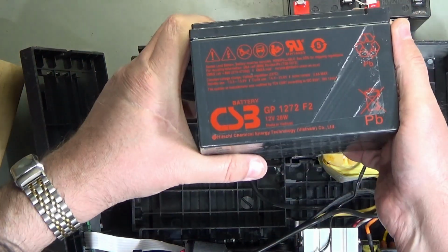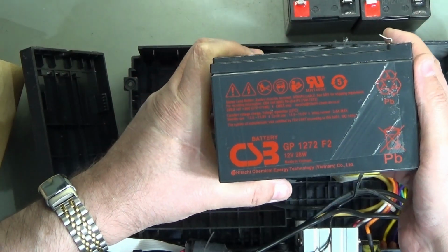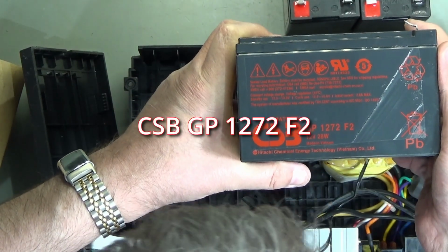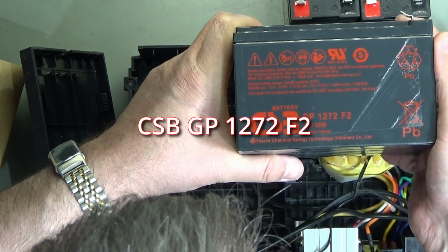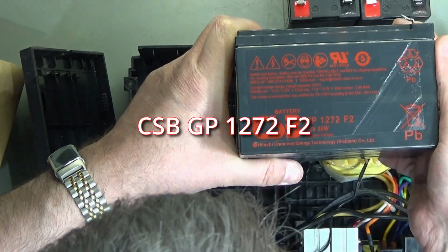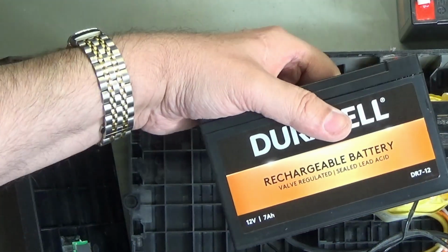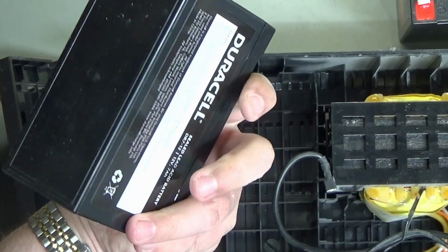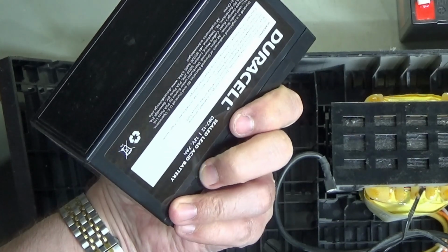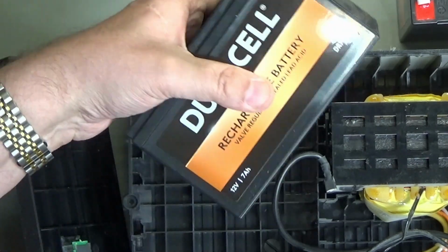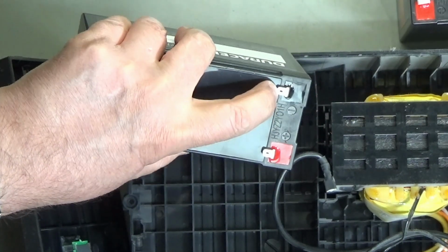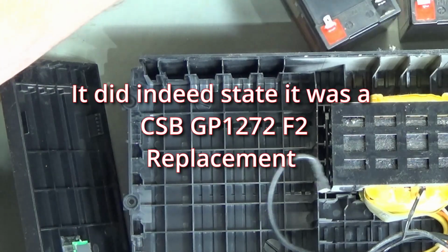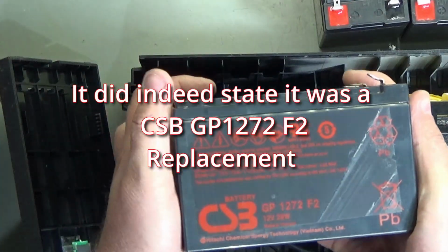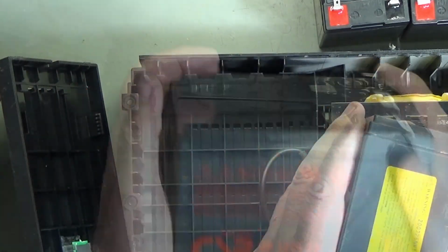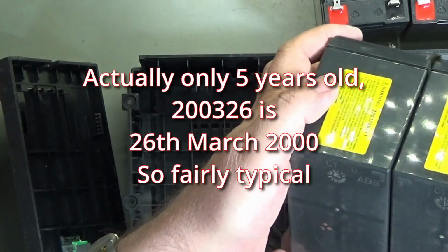So there we go. These are Hitachi. They're CSB batteries. GP1272F2. So my new ones are also 1272s, of course. And exactly the same capacity. The only difference being, I think these are called F1 connectors on the top. I'm sure it said F2 when I ordered them, which is really, really annoying. Here's our date code on the end there. So yeah, quite old.